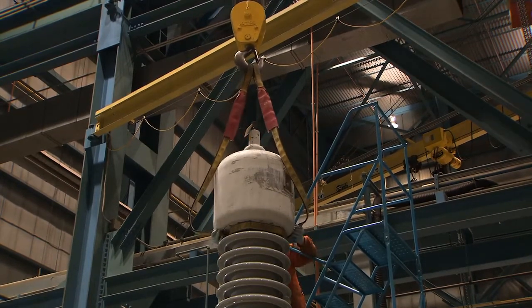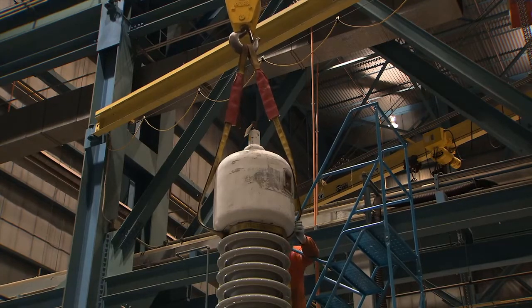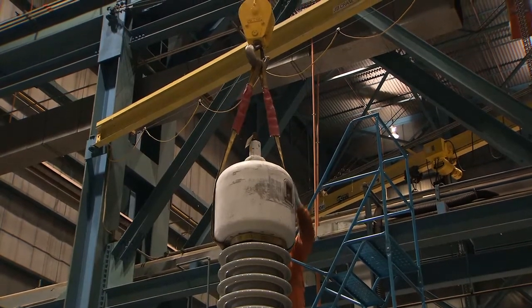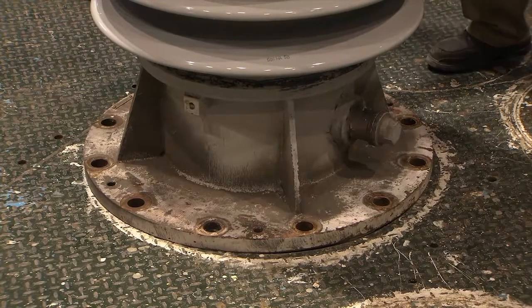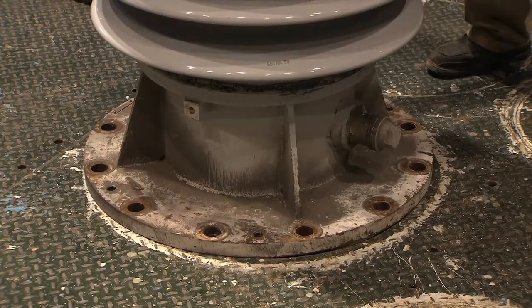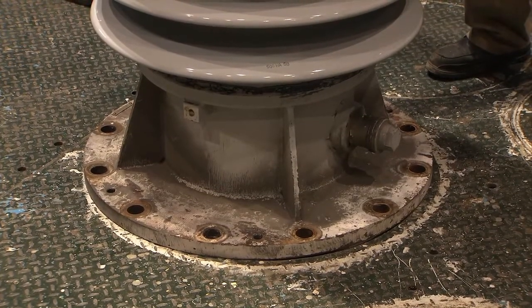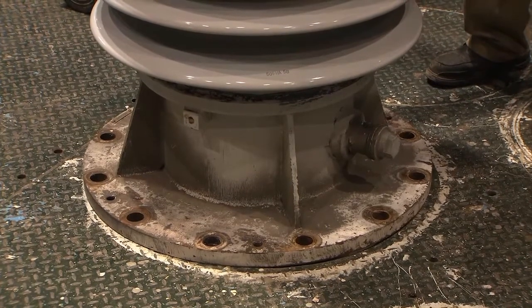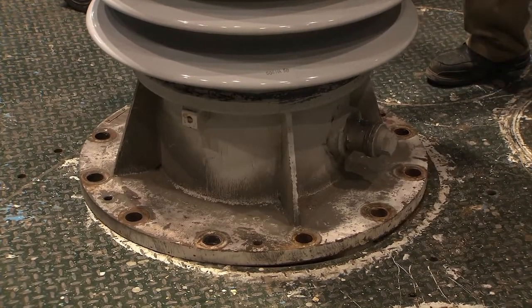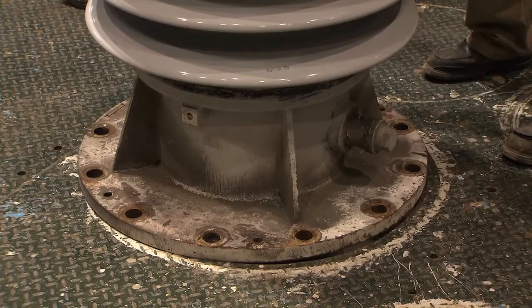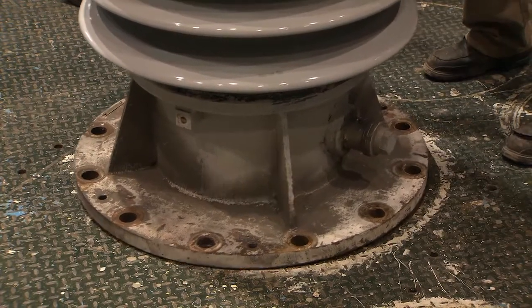The crane operator should begin to remove the slack in the slings by raising the hook. Okay, you ready? Yep. Okay, I'm going to lift it now. In very small increments, the crane operator can slowly lift the bushing a few inches upwards. Any necessary adjustments are made to keep the bushing centered in the service well.